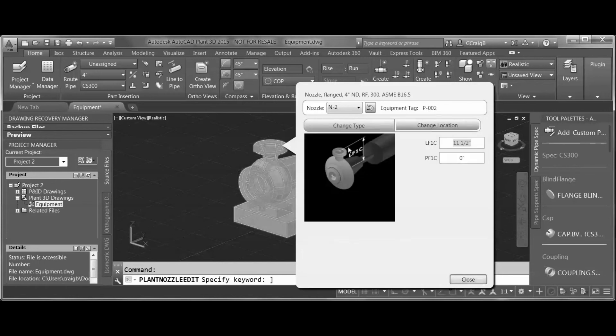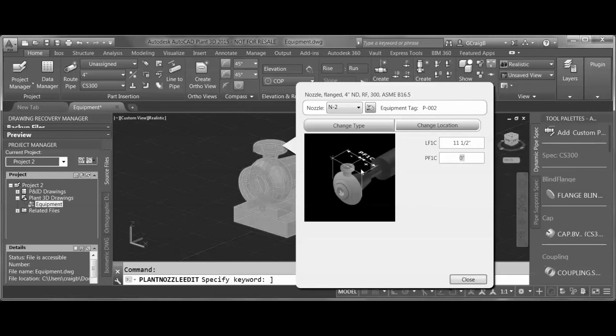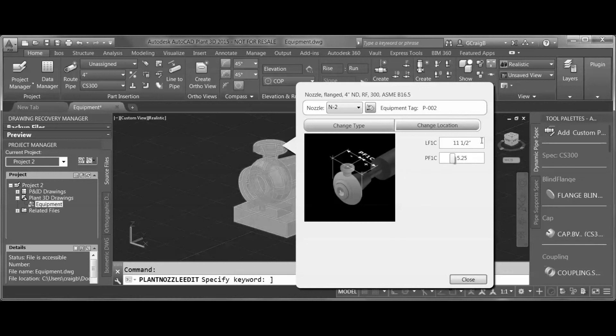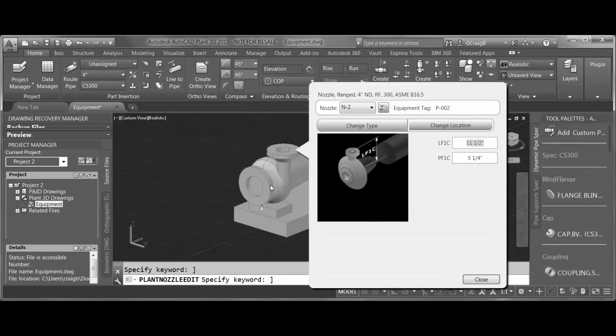In the Change Locations tab, I can set a height from center of suction to center of discharge, and I can also set an offset. This is where I can do a positive or negative value to, in a sense, create an eccentric discharge nozzle. I'll type a value in here and we'll see that nozzle comes off to the side as an offset discharge.